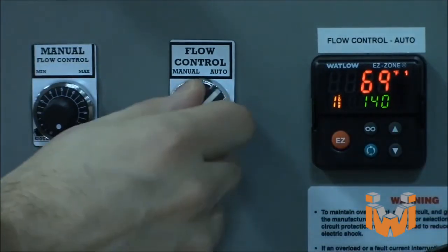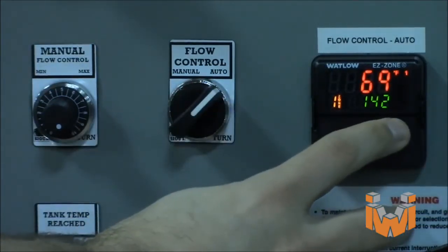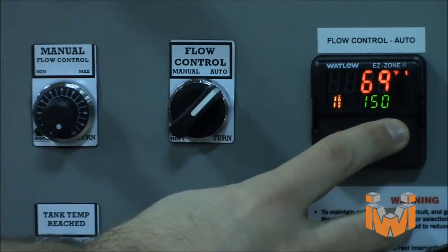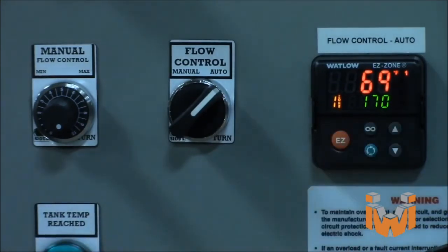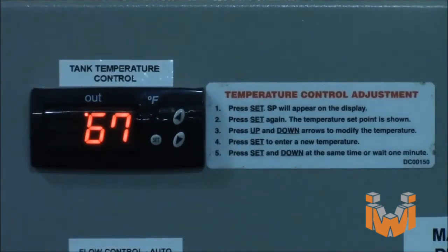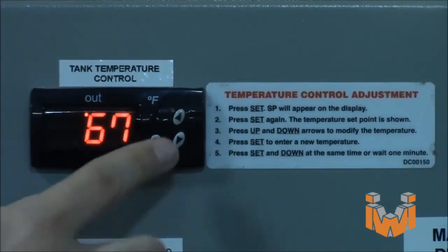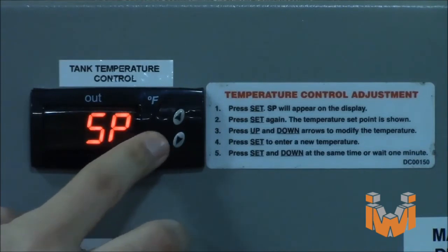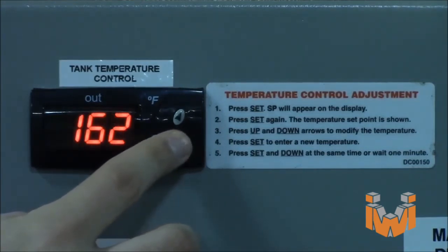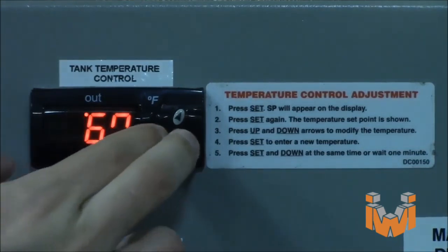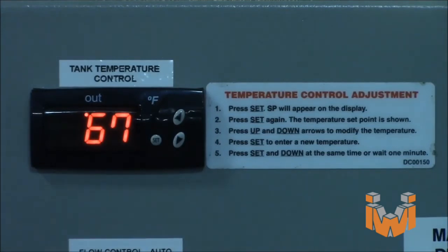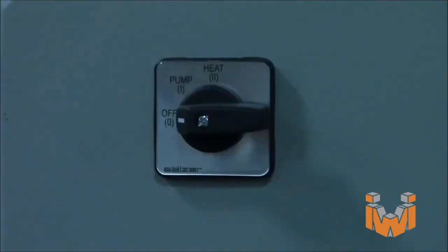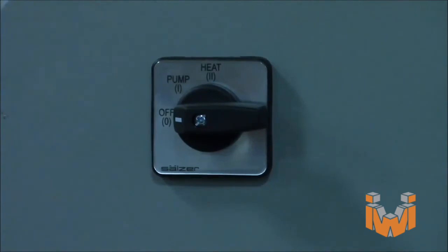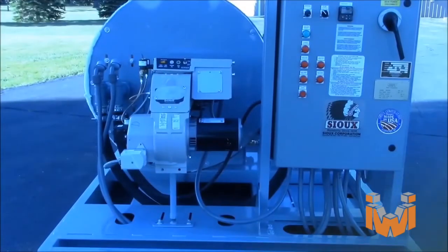For automatic mode, use the arrow keys on the controller to set the desired outlet temperature, shown in green, up to 190 degrees Fahrenheit. Follow the posted instructions to set the desired tank temperature by using the digital temperature controller in the top center of the control panel. During normal operation, this control will display the current tank temperature. Finally, turn the power switch to the pump position to start the pump motor. Turn the switch to heater to start the burner.